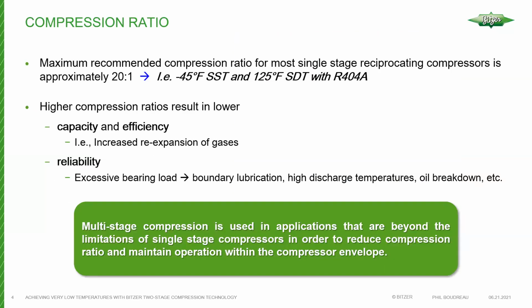So at first, we'll say the single-stage compressors, the limiting factor in their use is the compression ratio. And the higher the compression ratio, the higher the discharge temperature, the more leakage and more re-expansion of gases that takes place. So the efficiency drops off, to a point where you've got a fair amount of energy input into the compressor, but your output is very low. So very low efficiency. So the two-stage allows us to offset that substantially.